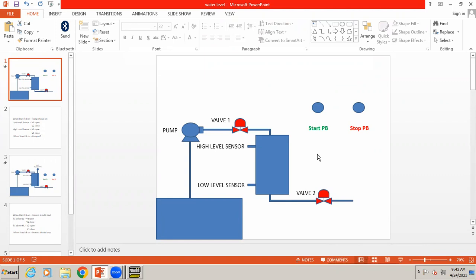When you press the start push button, the pump should start. Once the pump starts, it pumps water into the tank. Normally the tank is empty, so the low level sensor will be in the ON state and the tank level will increase. When the low level sensor is ON, valve one should open and valve two should be closed so the tank level increases. Once it reaches the high level sensor, valve one should close and valve two should open.